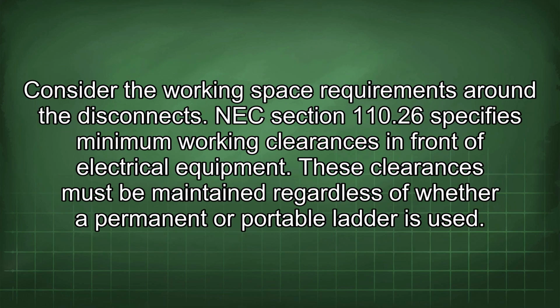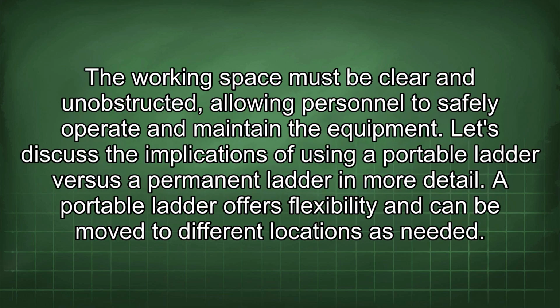Consider the working space requirements around the disconnects. NEC Section 110.26 specifies minimum working clearances in front of electrical equipment. These clearances must be maintained regardless of whether a permanent or portable ladder is used, and the working space must be clear and unobstructed, allowing personnel to safely operate and maintain the equipment.